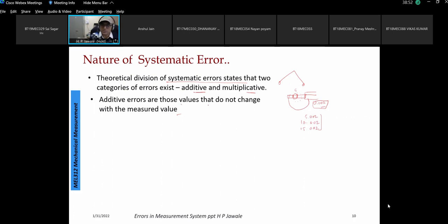So that is the meaning: additive errors are those values that do not change with the measured value. Even if the input changes, or stays the same across multiple readings, the error remains the same. For example, measuring a 5 millimeter bar diameter 10 times, all 10 readings will be very close to, or exactly, 5.002. These are additive errors — the error value does not change whether you change the input or repeat the same input multiple times.